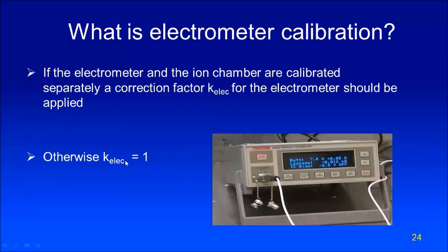The second influence quantity factor is the electrometer calibration factor. As explained earlier, this is needed only if the electrometer is calibrated separately. Otherwise the electrometer calibration factor will be one, because most often we do the electrometer calibration along with the ion chamber.